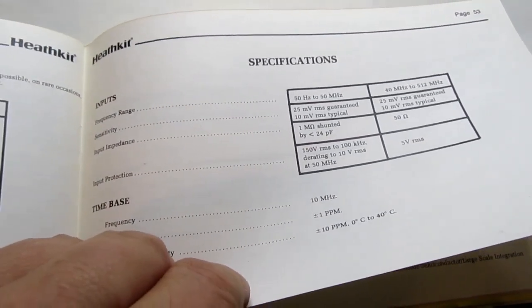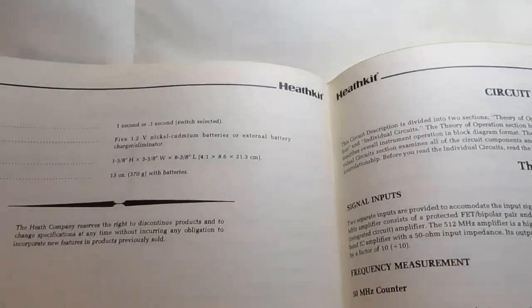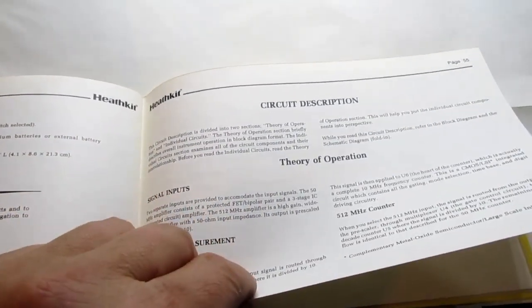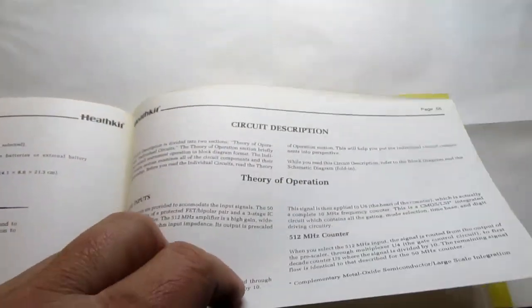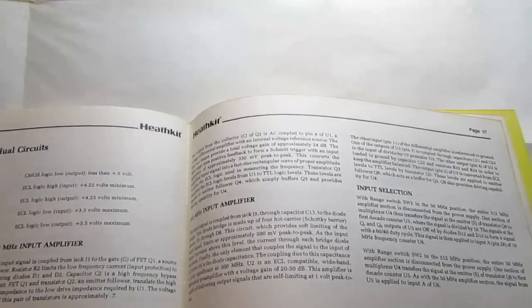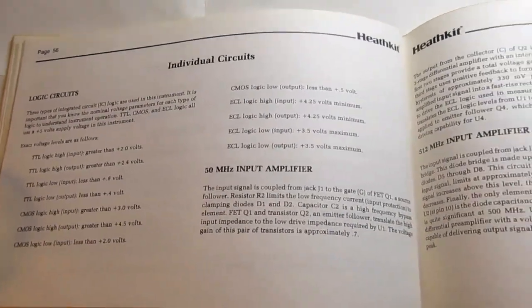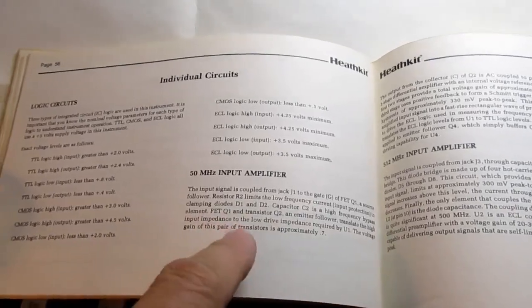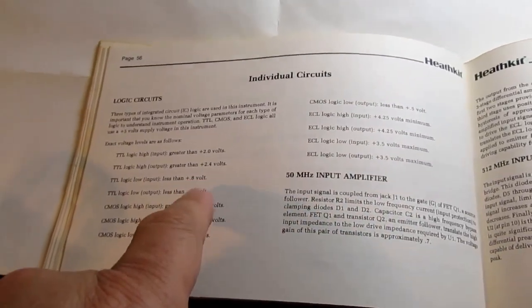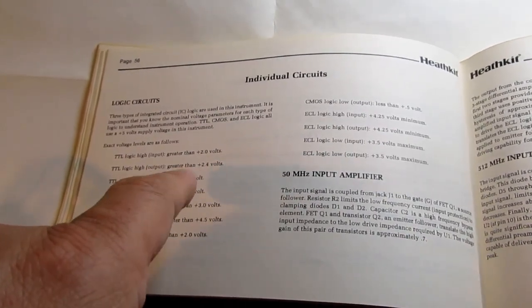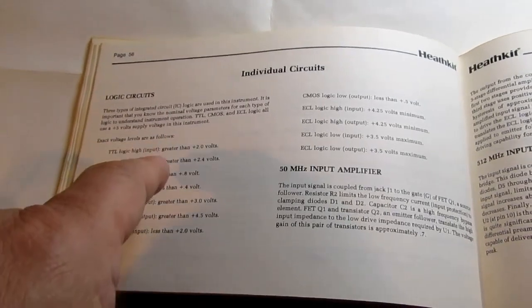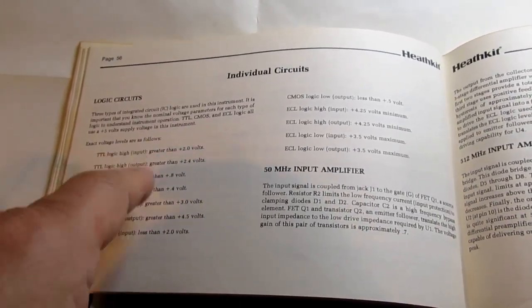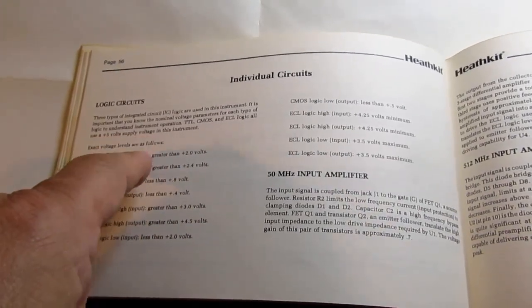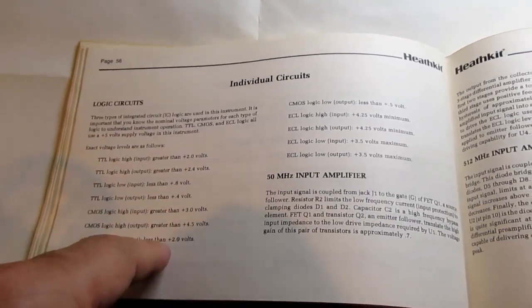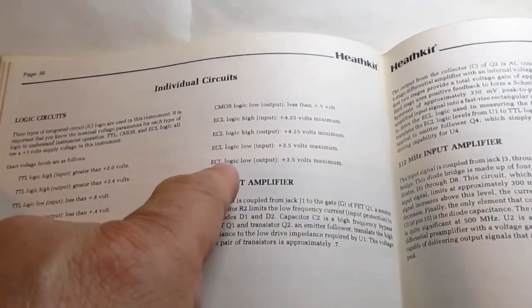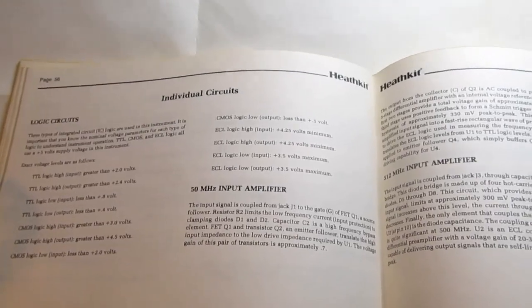Simple page of minimal specifications. Flowing over to the other side, a general theory of operation just on one page, talking about the essence of how it works. And then it has a nitty-gritty, more detailed circuit description of each section. It talks about how there's actually different digital signal levels you might want to read, and how that influences the input. And it also talks about within the meter itself, it's using TTL logic, CMOS logic, and ECL logic. And the ECL is used especially on the higher frequency stuff.